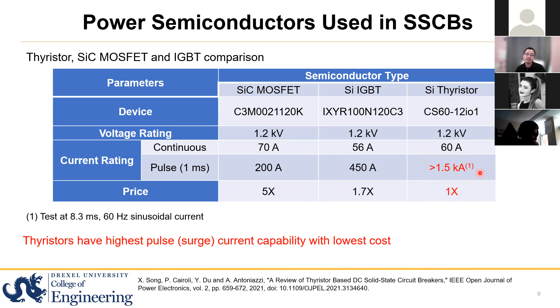That's why it still has a lot of advantages, not only from the price perspective. If we look at price, taking the thyristor as one unit, IGBT is 70% higher, and the recent silicon carbide device is 5 times larger. Even though we can withstand this higher cost, the pulse current capability of the thyristor is still super high.